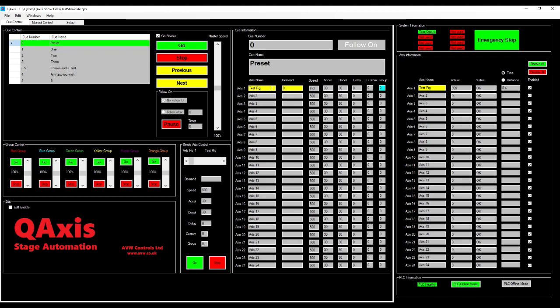And if we want to send it back to zero, put the preset position in. We've got zero here. This time we've got a speed of 87.2% with three seconds of acceleration and three seconds of deceleration. So if we send it off it will do it now in 8.4 seconds. So it will take slightly longer. And we press go. It's taking longer to accelerate. And longer to decelerate.